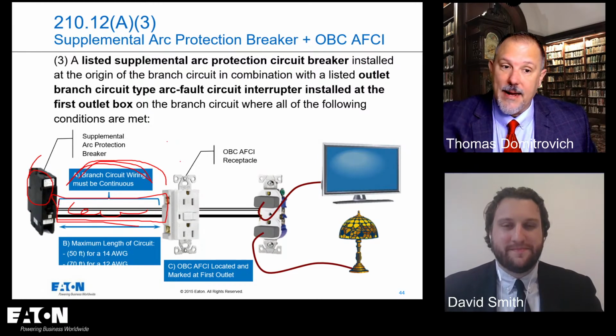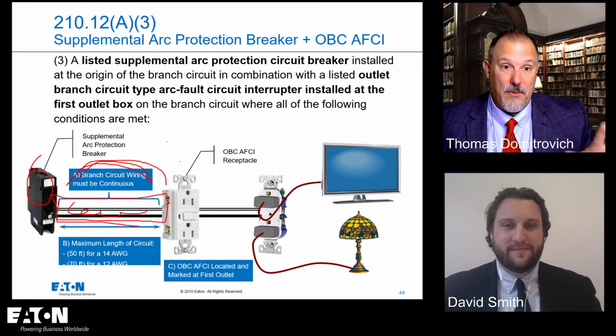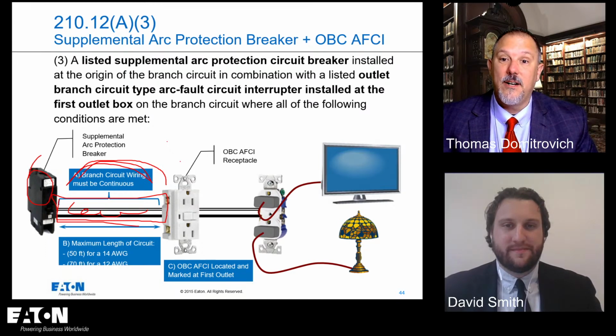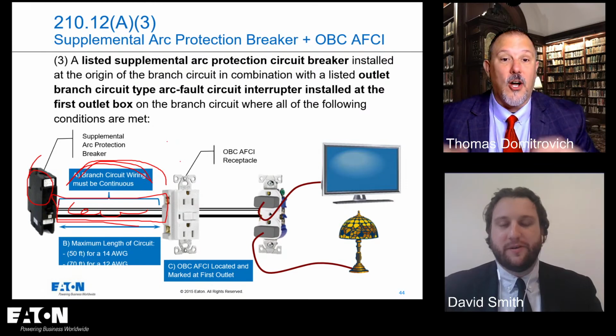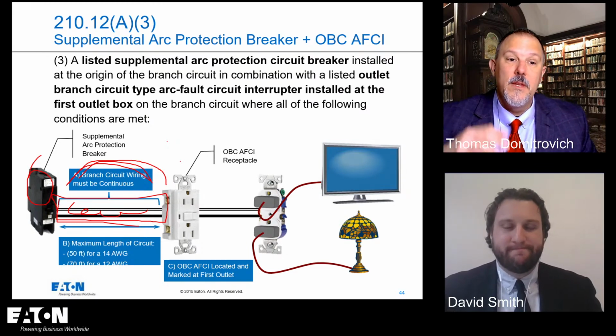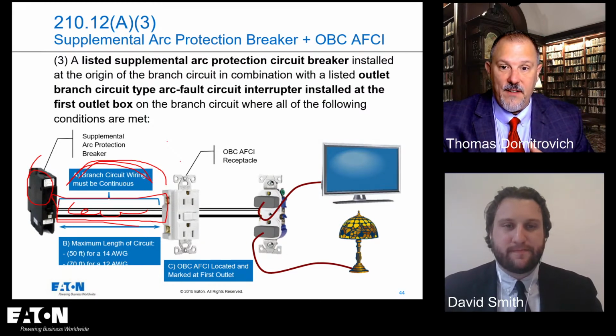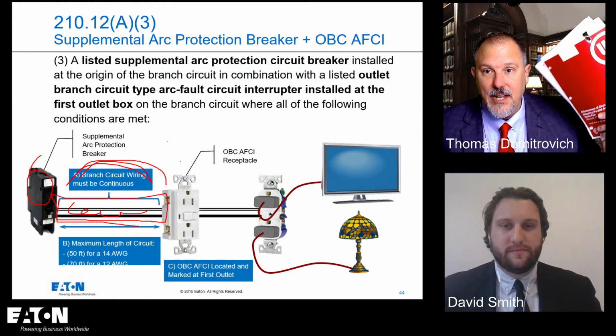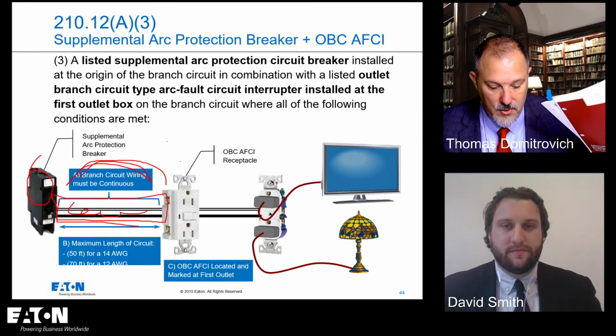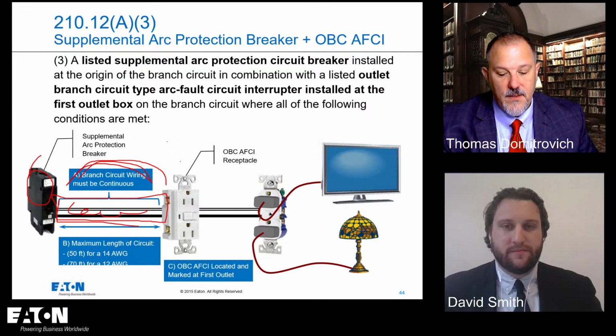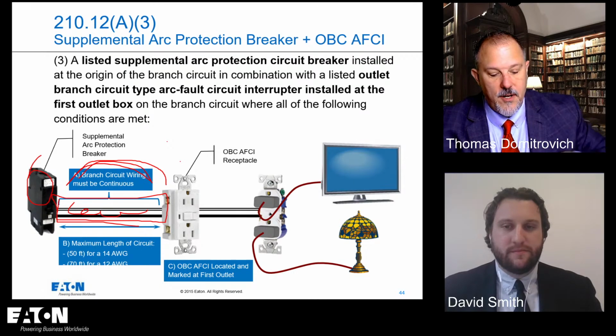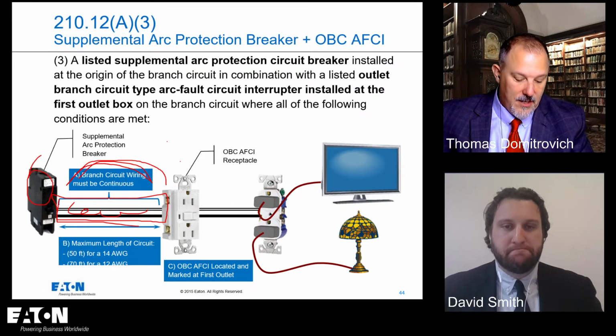I mean, I went back, and so all of this research somehow, and I think it's just because of, you know how it goes, arguing, debating back and forth, we ended up with 50 and 70 feet based upon equations from UL test reports. The effectiveness of circuit breakers in mitigating parallel arcing faults in home runs. This was January of 2012, revision 11.